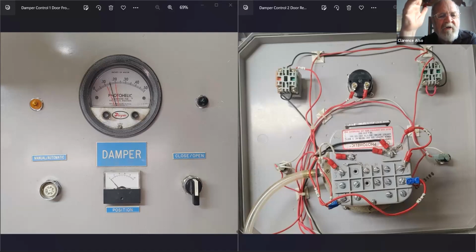BTUs out of your fuel than you're getting right now, just by the way you operate your plant. And it was simple - I increased their production about 8% just by making an adjustment. That adjustment was that open-close switch; I opened it up. So all I did is open it up a little bit and the temperature of the mix went up. All that happened is we gave him more air - we didn't give him more gas.